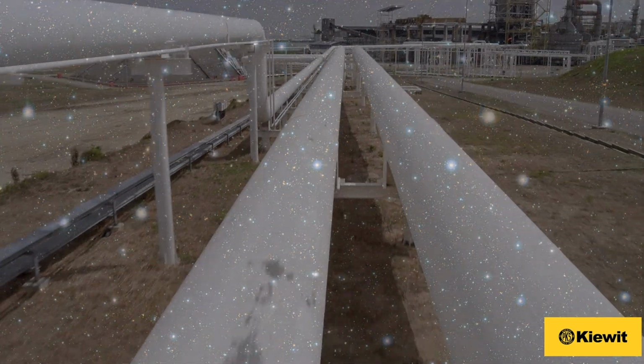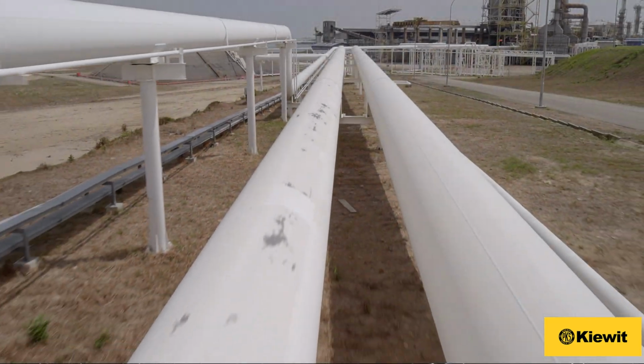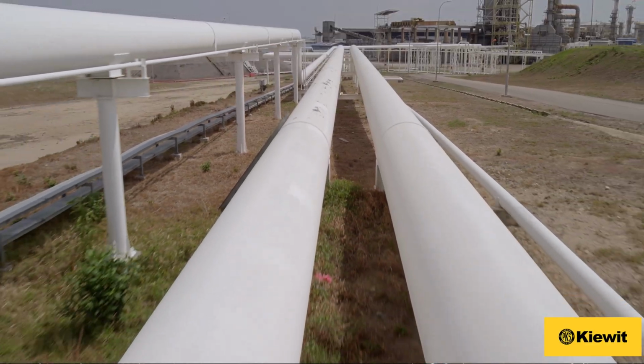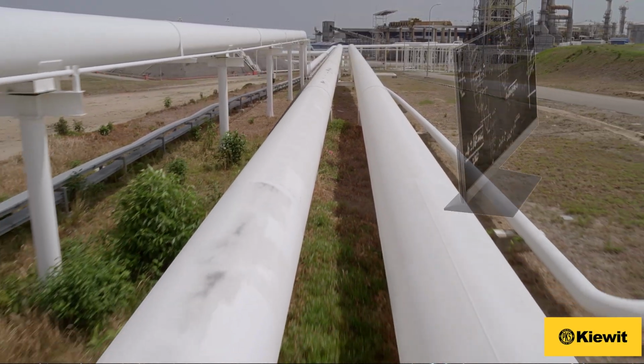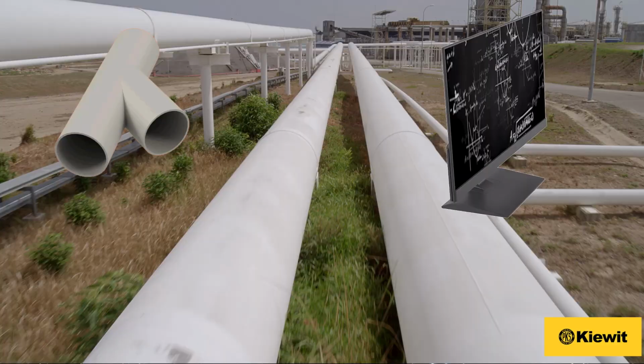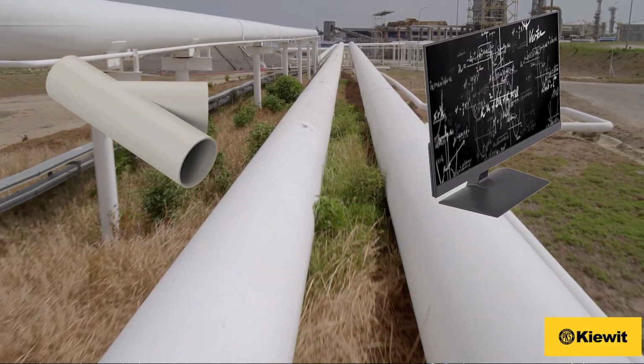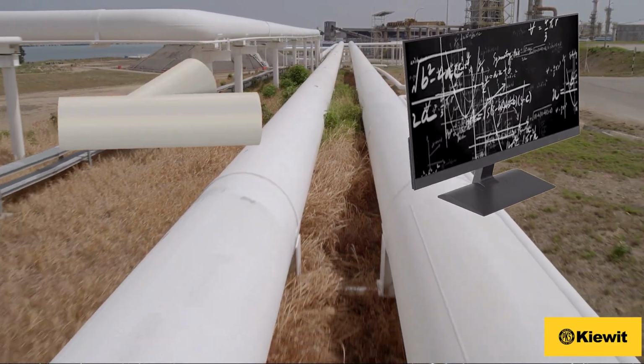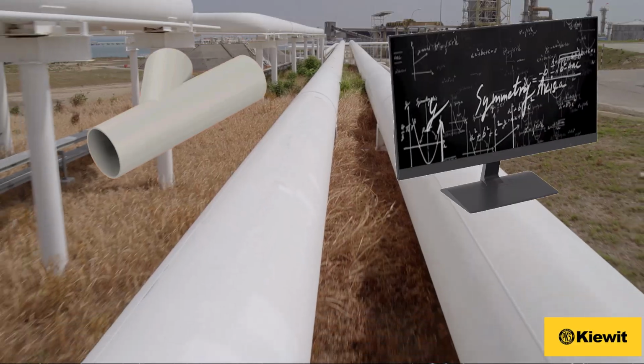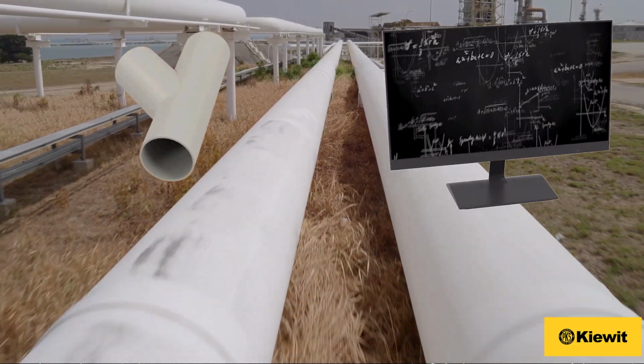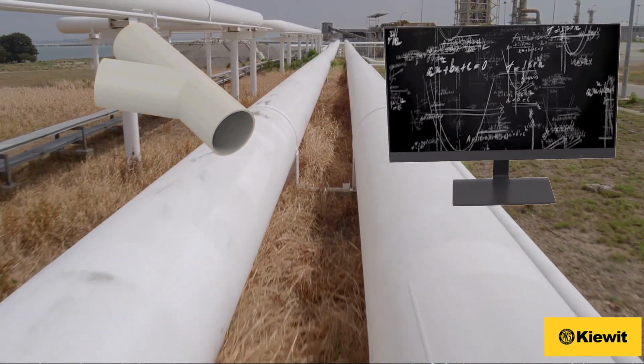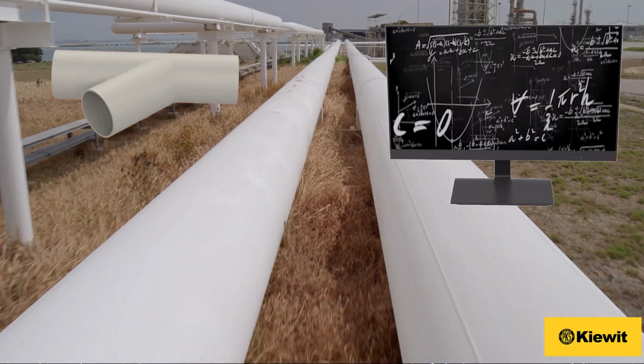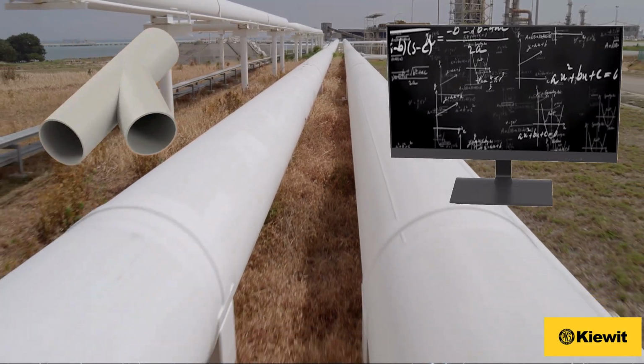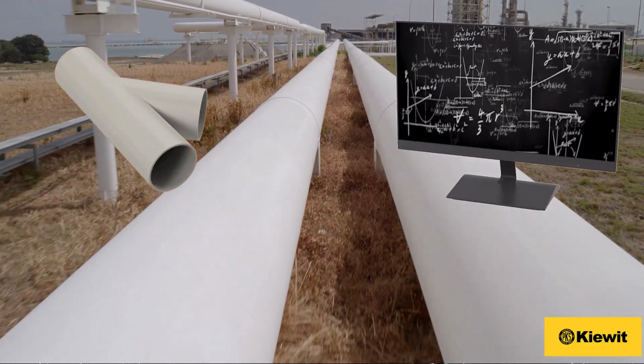When it comes to ASME B31.3, a lot of people are surprised to know that there are no stress equations for the effect that a fitting or a component might have in a piping system. It's all based on straight pipe only. But we all know that pipe fittings, elbows, in this case branches, all have local stresses.